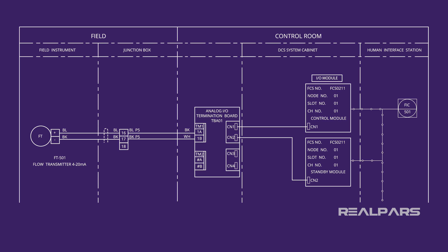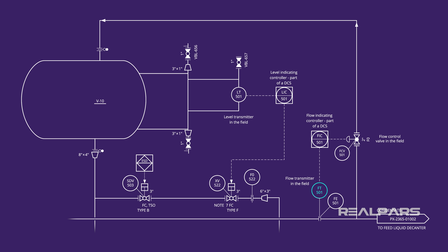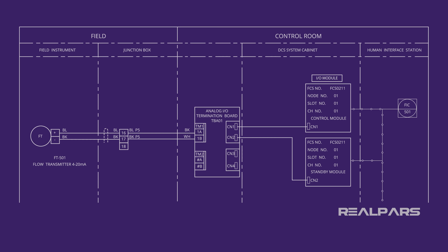Let's drill down a bit deeper and look at how the P&ID relates to the flow loop diagram. We've placed green circles around FT501 and FIC501. Referring back to the P&ID, you will see that FT501 is a flow transmitter in the field and FIC501 is a shared control in the DCS. This is a good time to point out the blue circle around the software signal lines as they show how the DCS connects with the HMI.